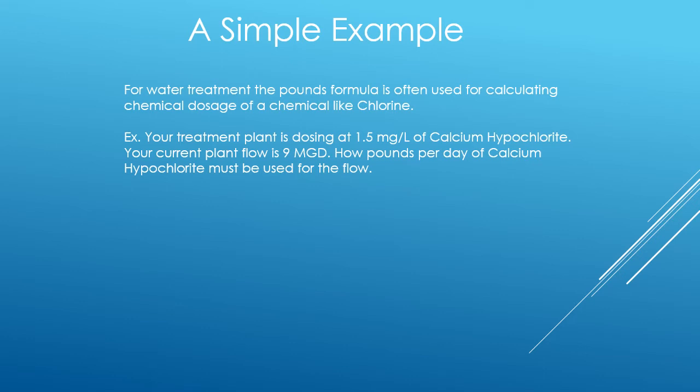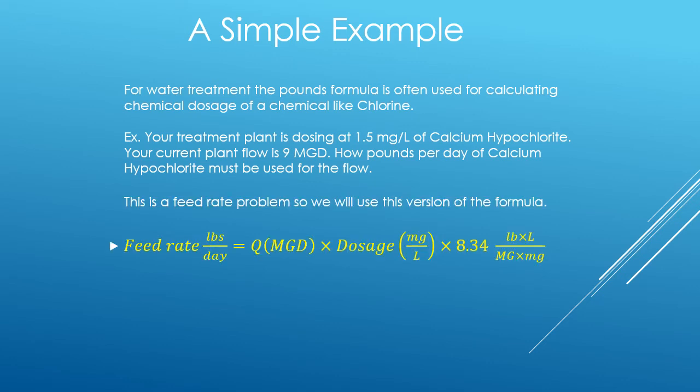Here's the example: Your treatment plant is dosing at 1.5 milligrams per liter of calcium hypochlorite. Your current plant flow is 9 MGD. We want to know how many pounds per day of calcium hypochlorite must be used for the flow.